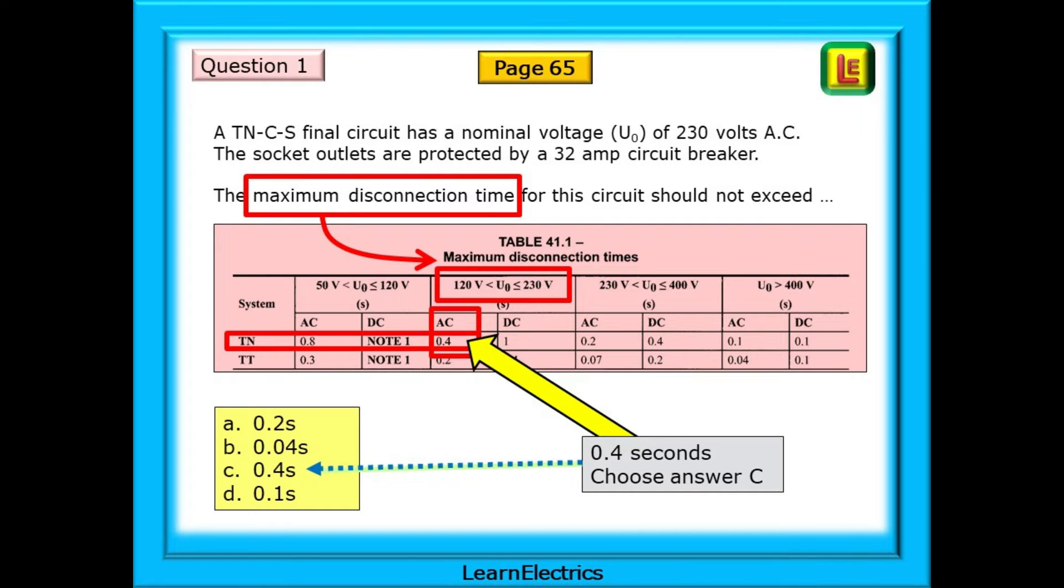All the information that we need is in the question. It's a 230 volt nominal circuit, so we want the second block of data, with the voltage between 120 volts and up to, but not exceeding, 230 volts. It's an AC circuit, and the question tells us it is TNCS, so the TN row is the one that we want. Where the AC column and the TN row cross is our answer, 0.4 seconds. This is our answer, and we should choose answer C.